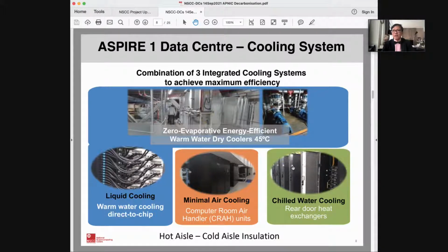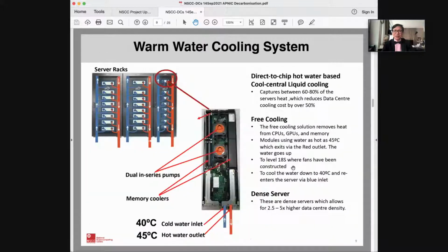We use zero evaporative, energy efficient warm water dry coolers, expelling heat at 45 degrees. The warm water cooling system goes directly to the computer chip, as you see in the middle of this slide, and the heat exchange takes place at 40 to 45 degrees.